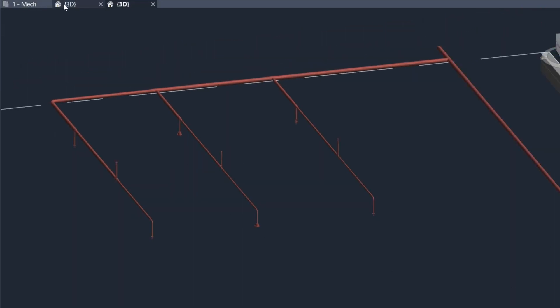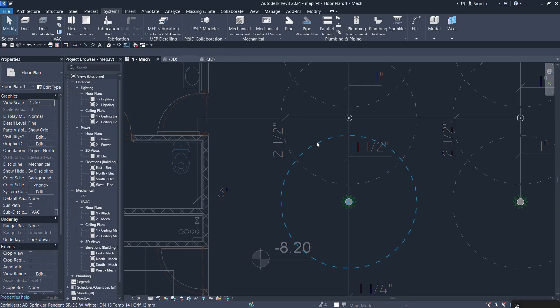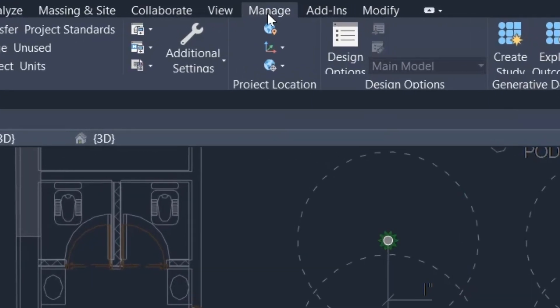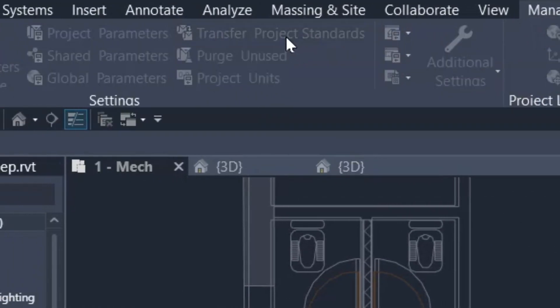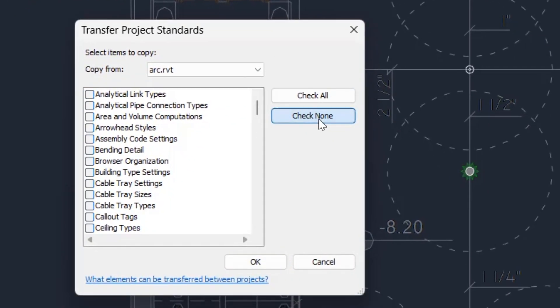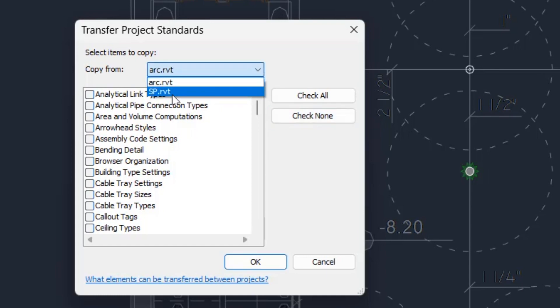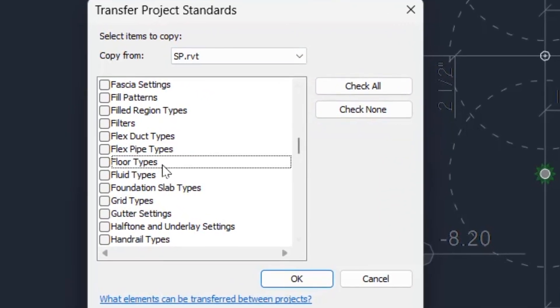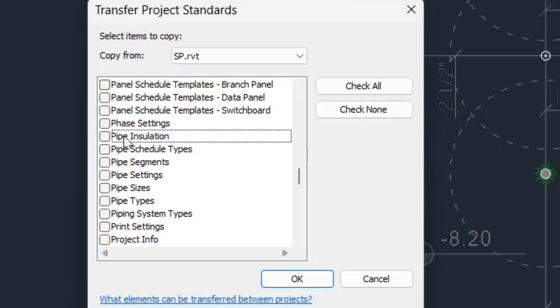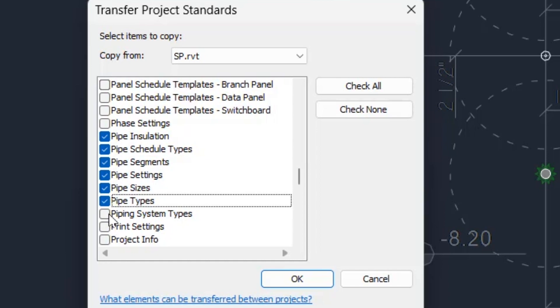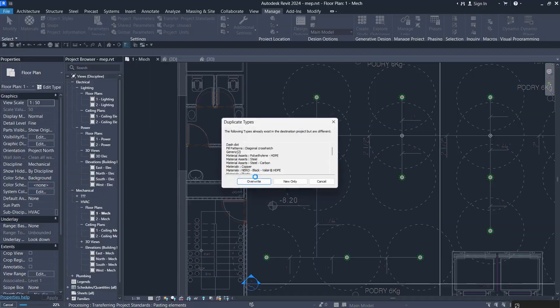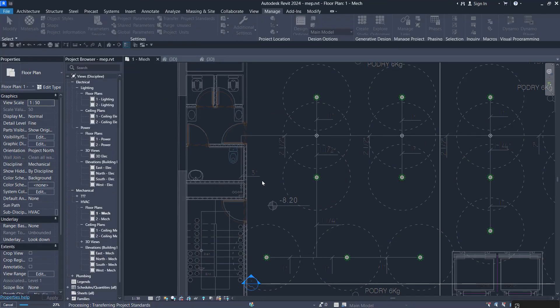To bring these families into your project, go to the Manage tab and click Transfer Project Standards. Click Check None and select the source project — sp.rvt. Check none to clear the selection, then go to Pipes and select all pipe insulation, schedule type, pipe segment settings, sizes, types, and system types. Click OK to bring in all the families.